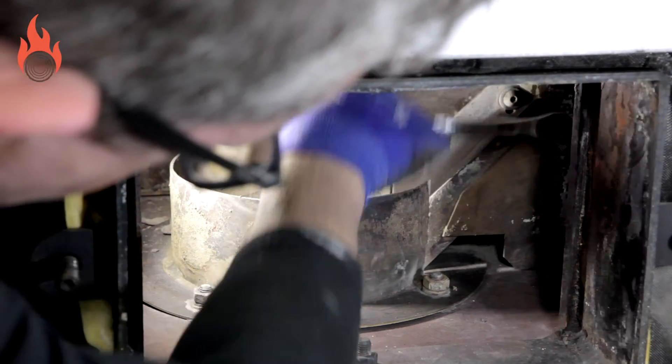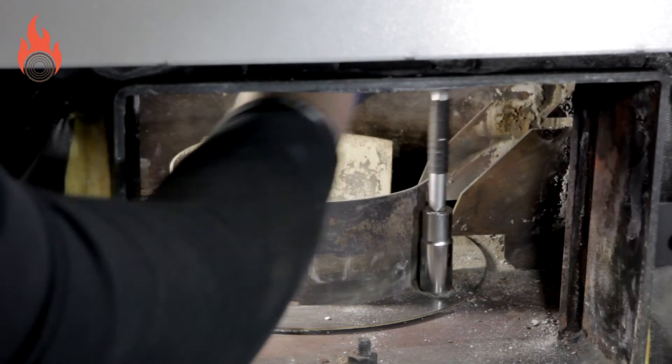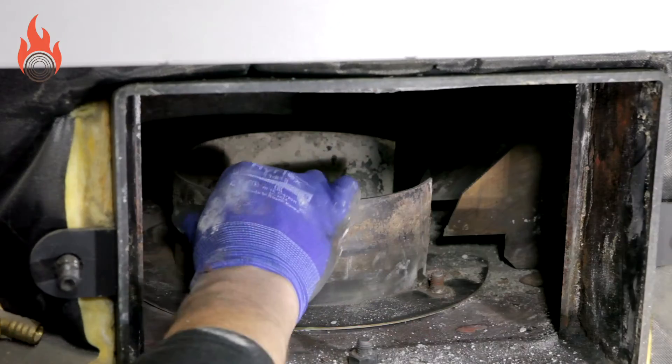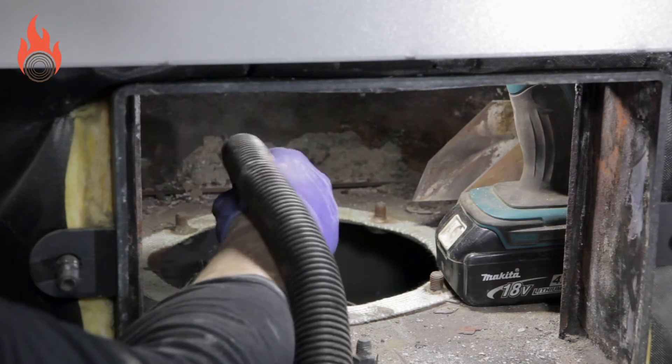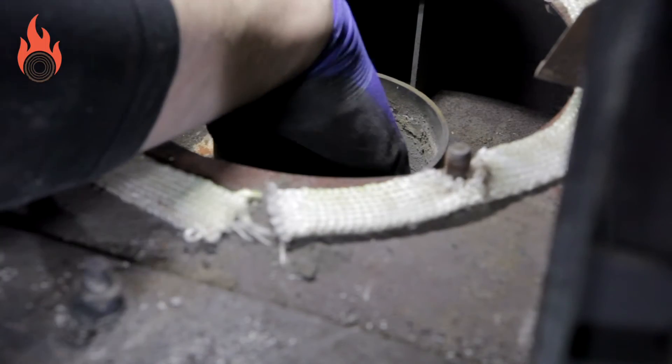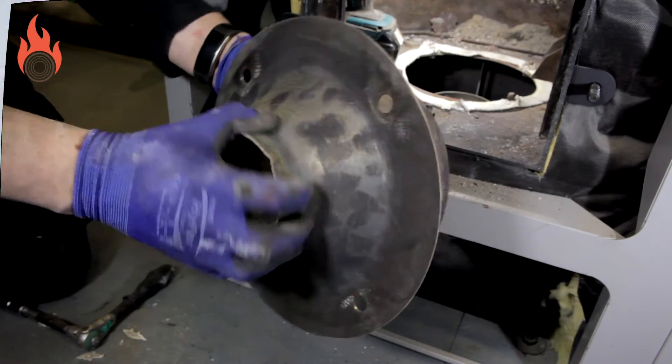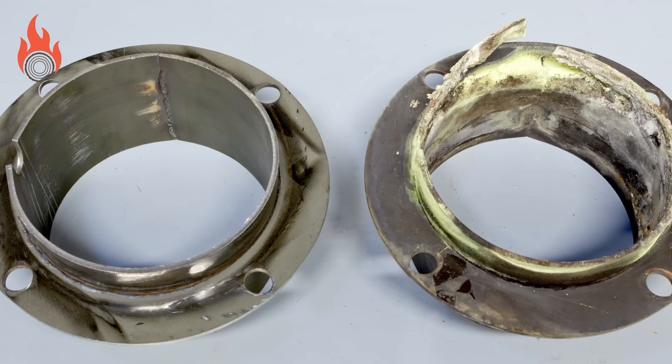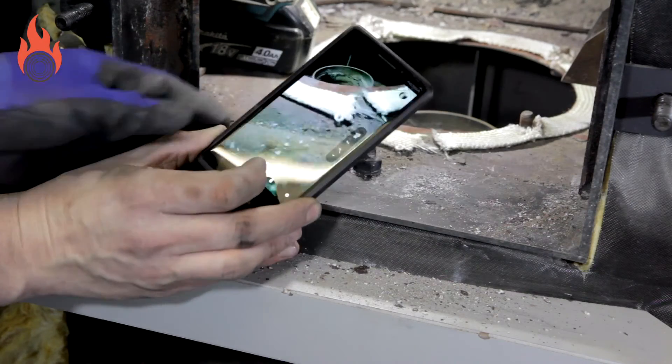You can now remove the pellet chute. Remove the upper burner bowl. Check for debris in the secondary air area and inspect the igniter tube for debris. Visually inspect the upper and lower burner pots for signs of wear. You are looking for any worn through sections that would cause a change in airflow around the combustion chamber. Also check the grate for signs of wear.